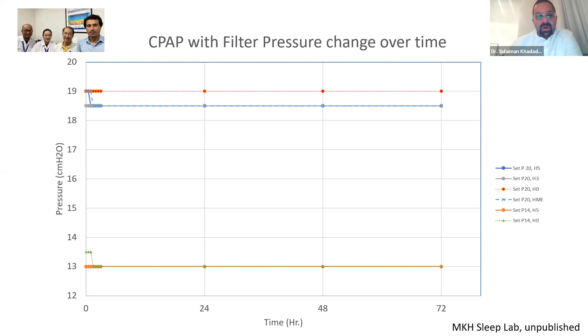So here I've shown you, in picture number 1 on the right-hand side, we've used a filter approximately near the machine. And you can see the main problem is you can't use a heated tubing when you use it like this. Picture number 2 is when we've done it without the humidifier, using an HME filter setup. If your patient, however, wants to use the heated tubing, you might consider doing what we've done in picture number 3, which is basically put the filter more distally.